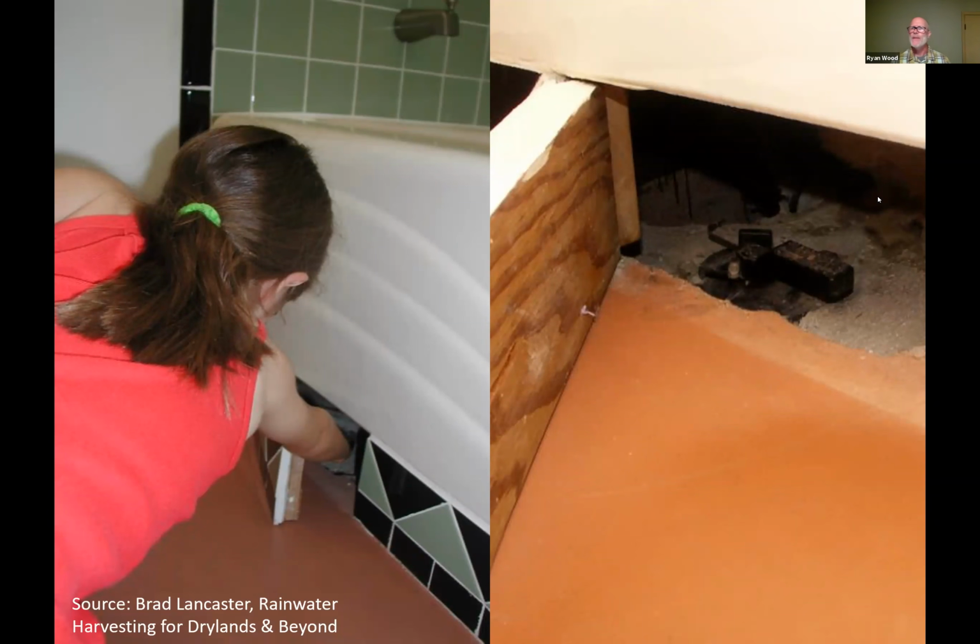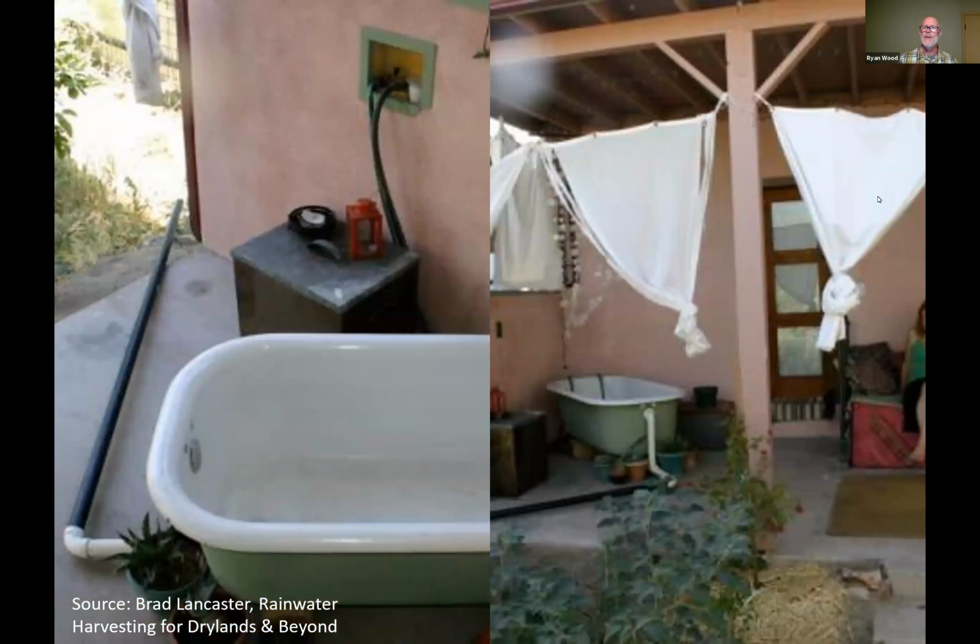This is a system that's not necessarily simple. This is more the complex way of using the shower gray water to get it out to the landscape, because you have to have a diversion valve. We need to be able to divert to sewer if the gray water system has a backup. So in order to get that valve to switch between sewer and landscape, they had to lift their shower or lift their tub up to get that space in between the tub and the floor to get the valve in. So if that's not an option, think about moving your tub outside.